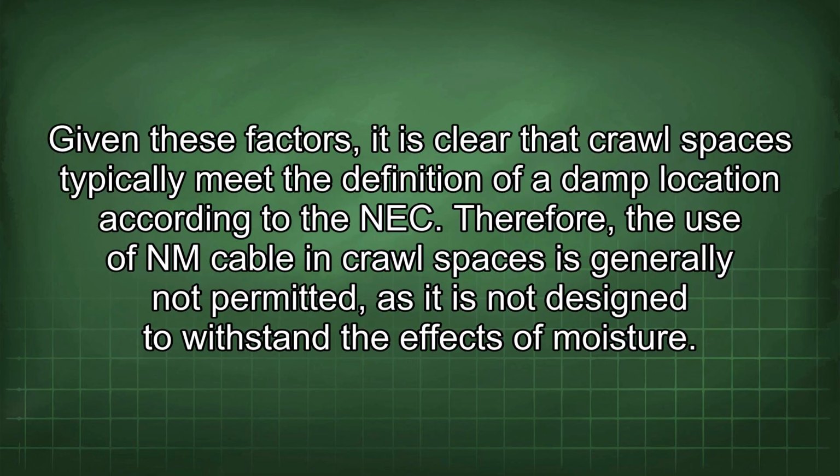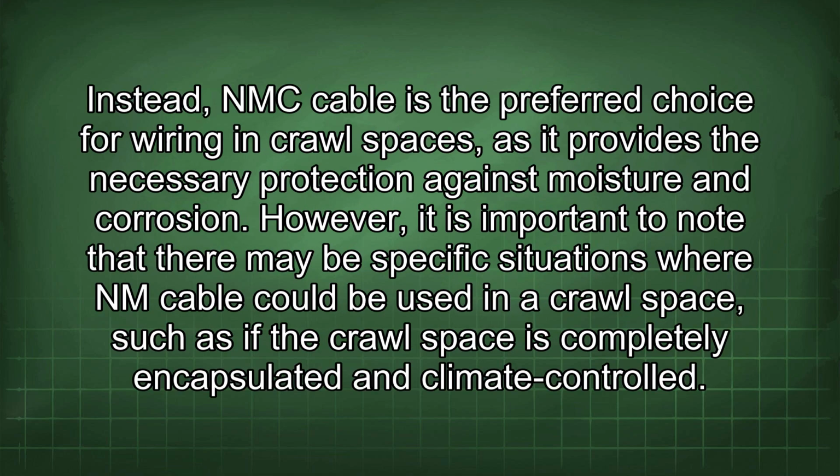Given these factors, it is clear that crawl spaces typically meet the definition of a damp location according to the NEC. Therefore, the use of NM cable in crawl spaces is generally not permitted, as it is not designed to withstand the effects of moisture.